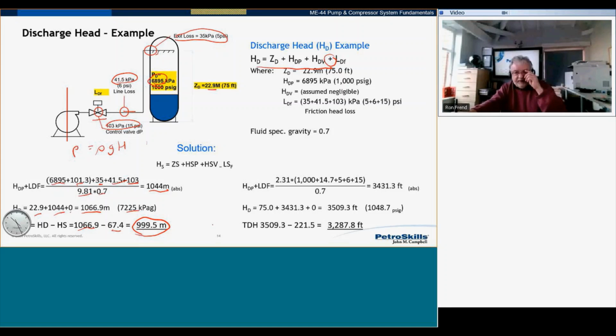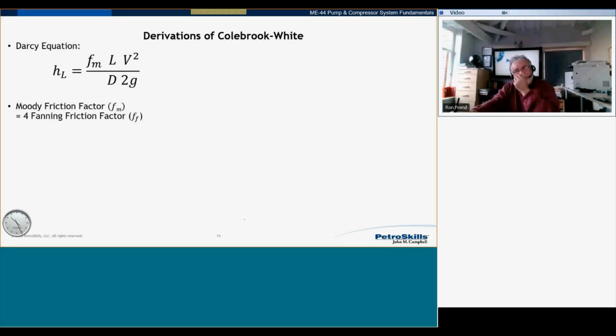And in fact, when we look at this, it is quite easy, isn't it? Because the height or the elevation of the liquid levels, I can measure. I've got liquid level gauges. The amount of pressure in the vessel, I can figure that out. I've got pressure gauges. It's the friction that's the problem. That does become problematic. Right, so what we're going to do is some calculations to figure out the friction head losses here, guys.